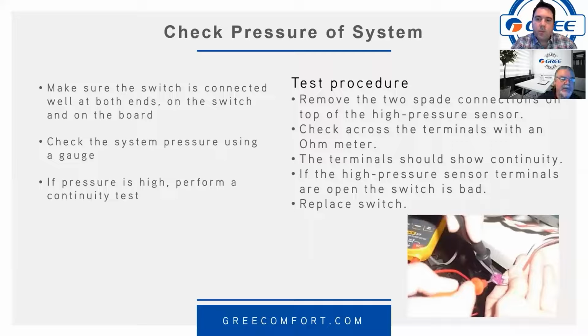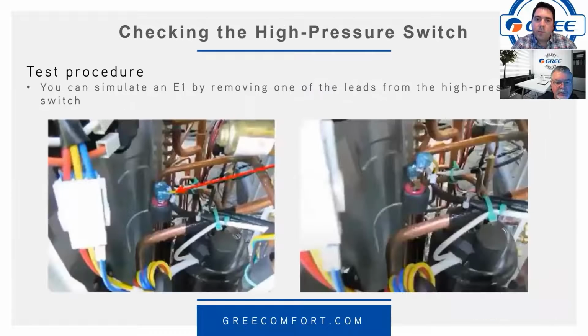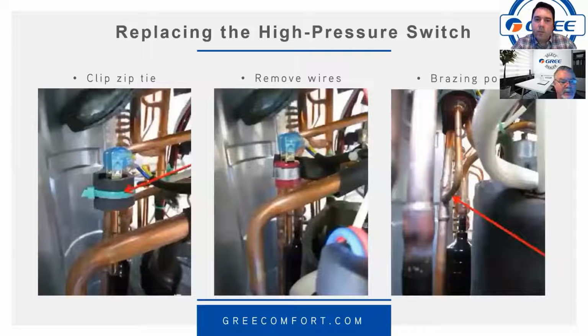And make sure the switch is connected well at both ends, on the board and the terminals on the switch itself. Check the system using the gauge. Pressure is high, again, that 600 range. You can perform a continuity test on that switch. Just pull the wires off, remove the two spade connectors and put the meter on there, and it should show continuity. If it does not, replace the switch. Another test you can do, you can simulate the E1 by removing one of the leads from the high pressure switch, if that is helpful.